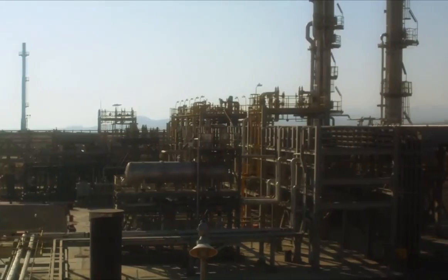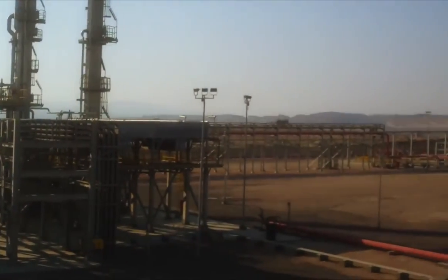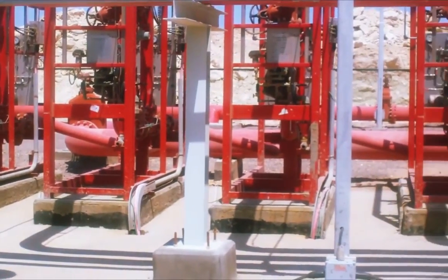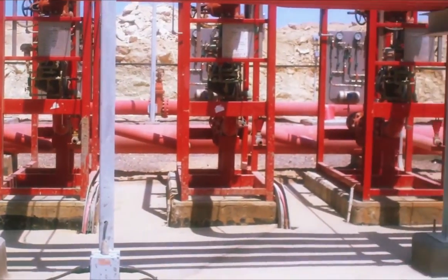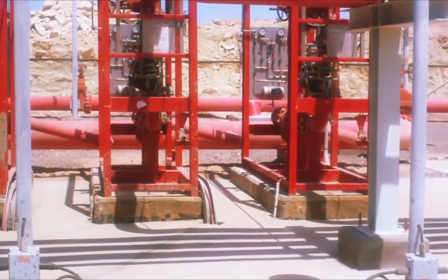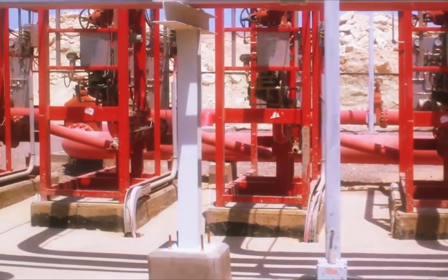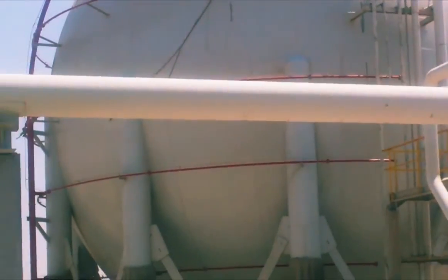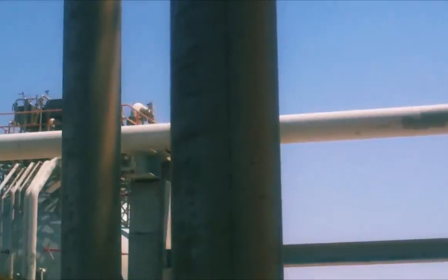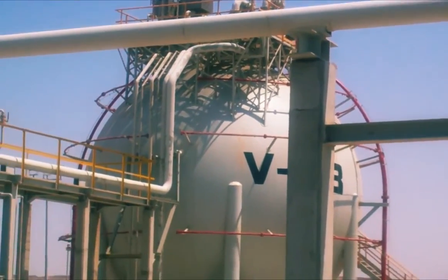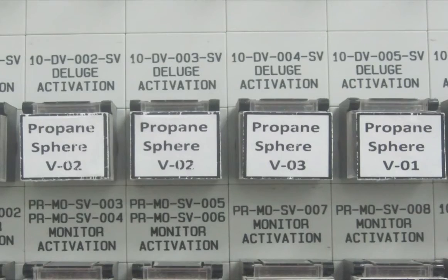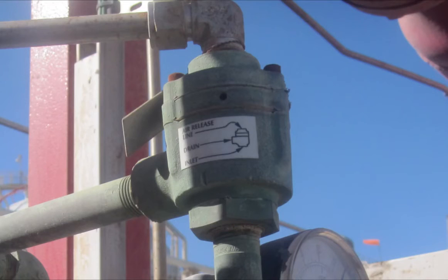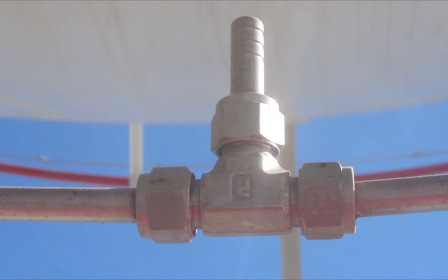In the Ibjetco plant, the deluge system is installed in 3 different areas. 5 deluge skids are installed at the storage area in order to cool down the temperature of the storage spheres, in case any temperature rise is detected. These skids are equipped with 2 methods of operation in order to increase the protection on the storage spheres. It can be operated manually from the control room by the solenoid valve or automatically by the dry pilot actuator in case a temperature element senses high temperature.